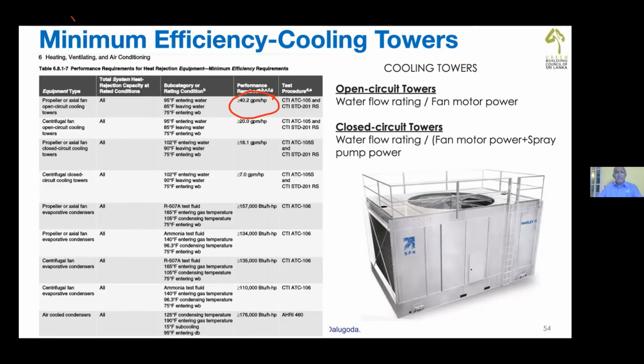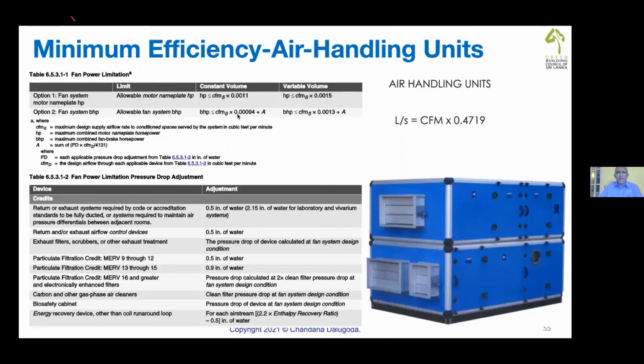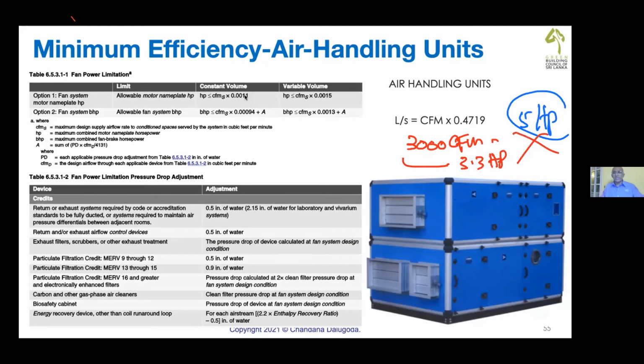Air handling units. Similarly, you have the same thing. Constant air volume, normal air handling units. Horsepower can be calculated. How? Supply CFM multiplied by 0.0011. Say, for instance, we have a 3000 CFM AHU. Now, constant volume, 3000 multiplied by 0.0011 gives you 3.3 horsepower. But when you check, it is a 5 horsepower fan motor. So it is not complying. No, it is having more power, huge power consumption. No, this is the limit. You'll have to satisfy 90.1 with 3.3 horsepower. Yeah, that is how you apply this.